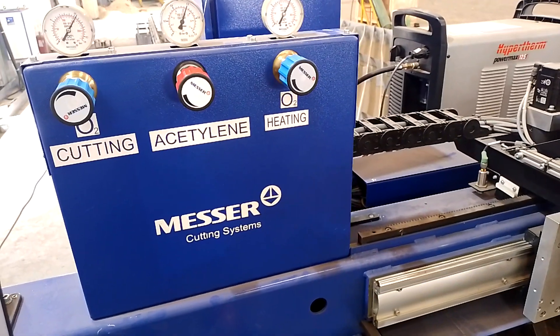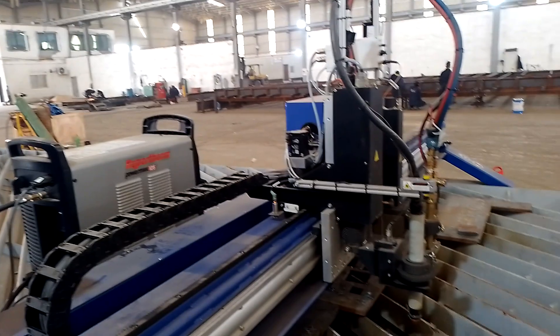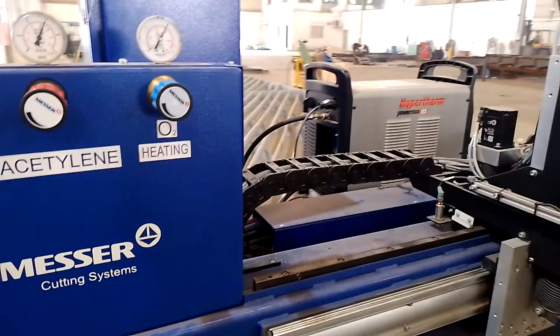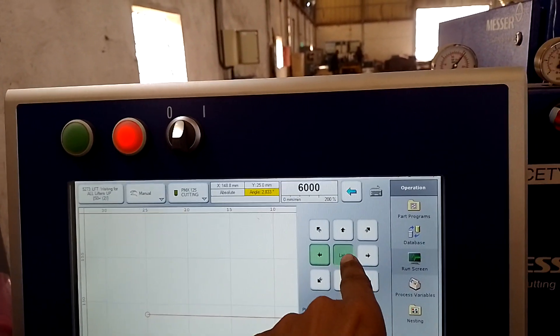See it will come back. The machine is going back, going forward. Latch, stop, latch — machine will come back. Same latch, latch stop. Latch right — Y axis going forward. Now latch stop. Y axis moving, stop. Now latch reverse and it is going in reverse. When it comes to the zero position it will automatically stop. Now it is giving an error here — latch finish and we can move it back.